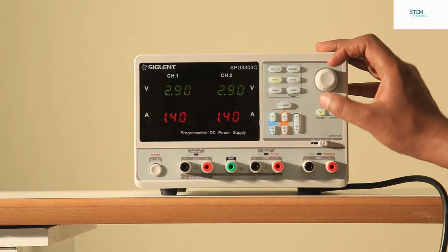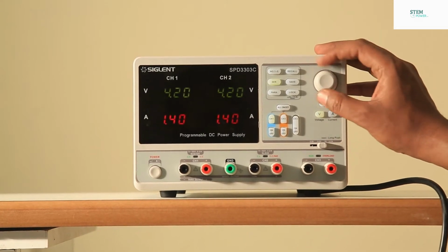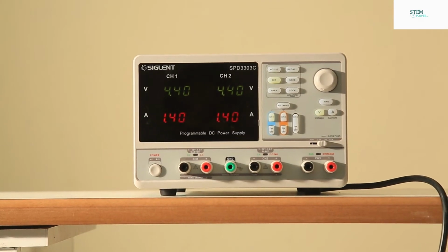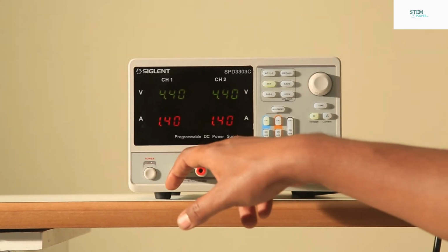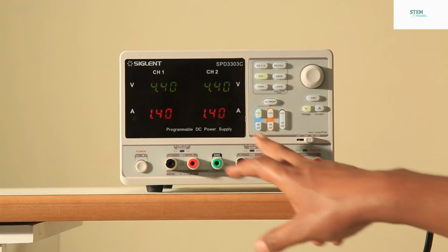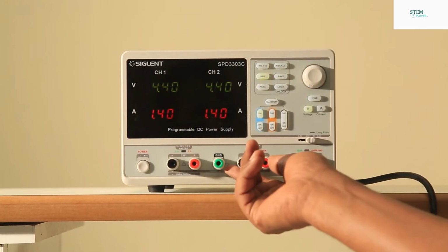Selecting the voltage, it increases—channel 2 is now giving 4.40 volts. In series mode, the master channel always controls the slave channel; channel 1 is the master and channel 2 is the slave.